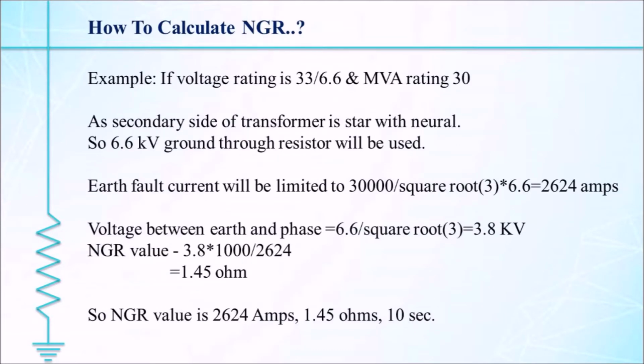Here is one example of calculation of NGR. If the voltage rating is 33 by 6.6 and MVA rating is 30, as the secondary of the transformer is star with a neutral, so 6.6 kV ground through a resistor will be used. Earth fault current will be limited to 30,000 divided by square root of 3 into 6.6, which equals 2624 amperes. The voltage between the earth and phase is 6.6 divided by square root of 3, which equals 3.8 kilovolt. NGR value is 3.8 into 1000 divided by 2624, which equals 1.45 ohm. So NGR value is 2624 ampere, 1.45 ohm, 10 second.